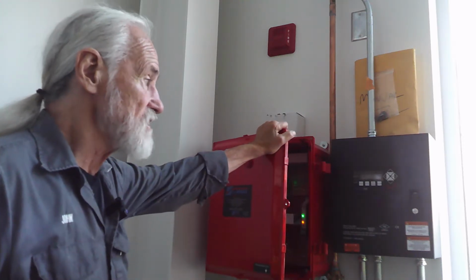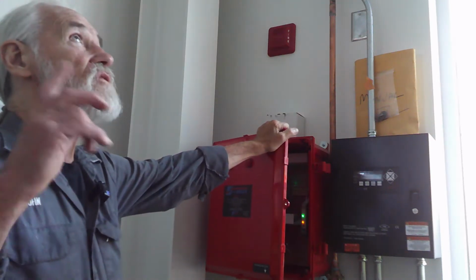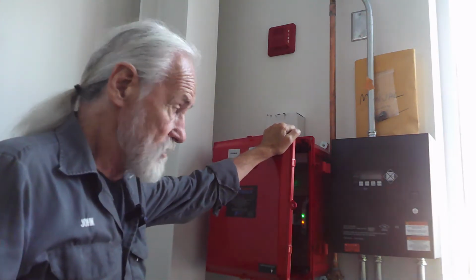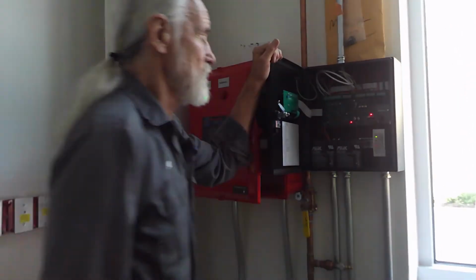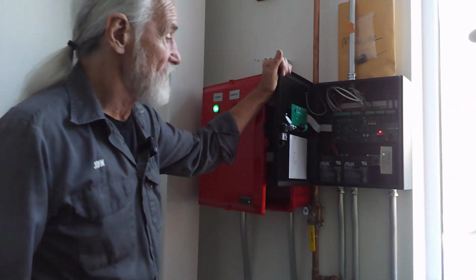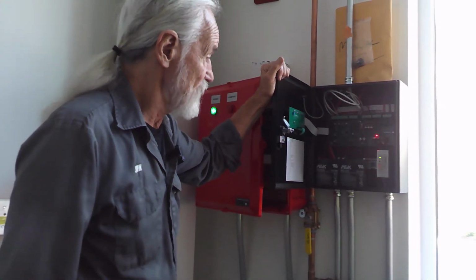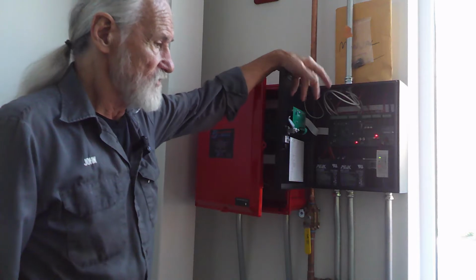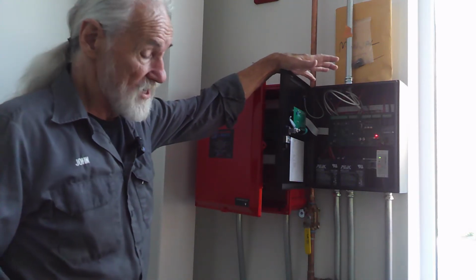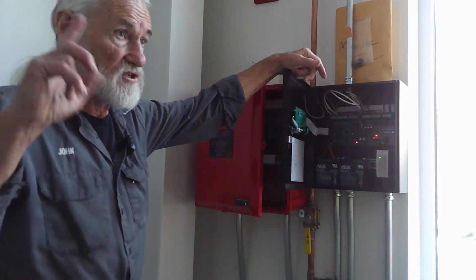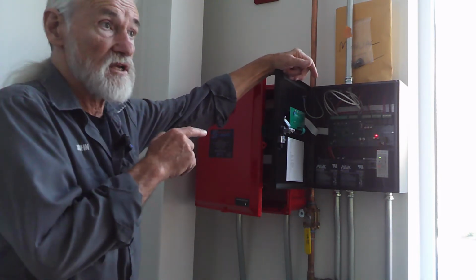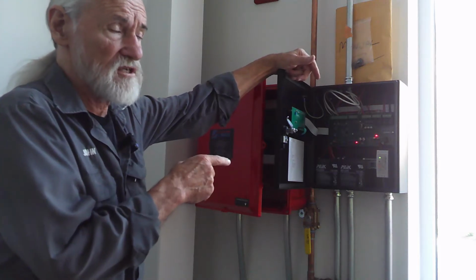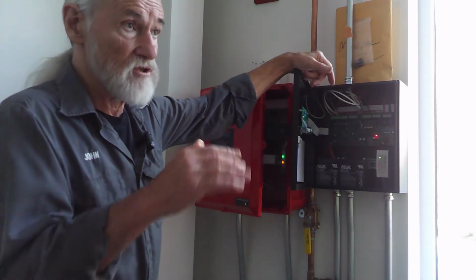It's extremely sensitive to the DC voltage of the signals - these spark detectors are DC, because it's got this computer in here. That board is all DC. So what has happened, and I've seen it happen a few times, is that if the high voltage wire, which is 120 volts AC, if someone has put it in the same conduit as the DC, it confuses this thing, and it interprets that as a fire. So it sets off alarms.